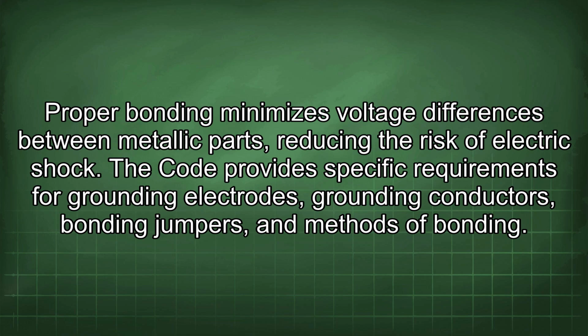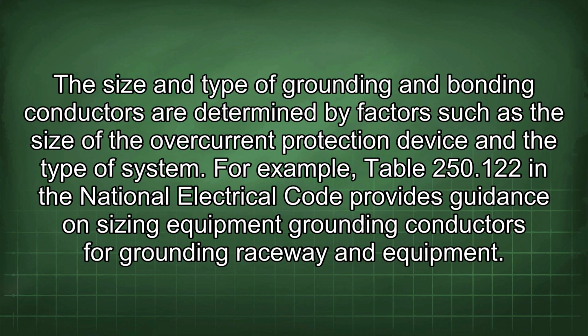The code provides specific requirements for grounding electrodes, grounding conductors, bonding jumpers, and methods of bonding. The size and type of grounding and bonding conductors are determined by factors such as the size of the overcurrent protection device and the type of system. For example, Table 250.122 in the National Electrical Code provides guidance on sizing equipment grounding conductors for grounding raceway and equipment.